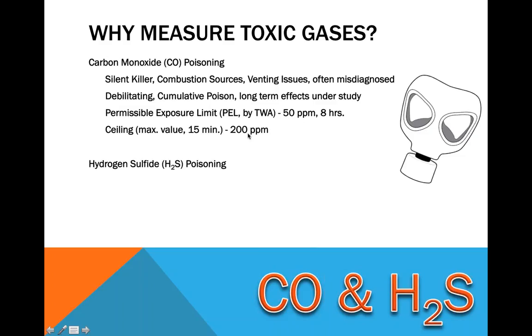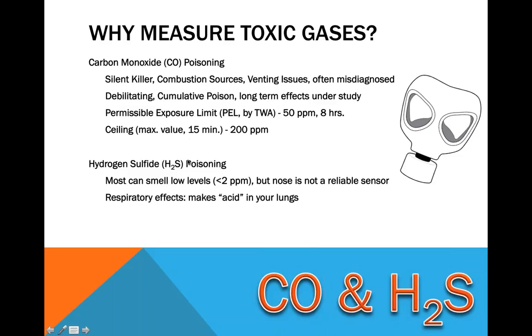system very quickly. Hydrogen sulfide is a gas that can be produced from biological sources and can also just be coming basically from sewage gas, that kind of thing. Most people can detect it with their nose at less than 2 parts per million, but the nose is not a reliable sensor in that the nose will get an olfactory fatigue. It'll just get tired of smelling the same smell and will no longer pick it up in the same concentration, so you cannot rely upon the nose. In carbon monoxide, there's no way of detecting it with the human body. It's not a gas you can detect with your nose or eyes.